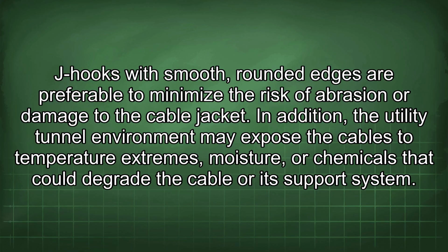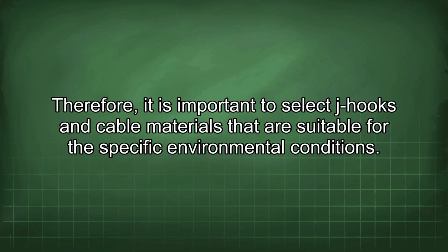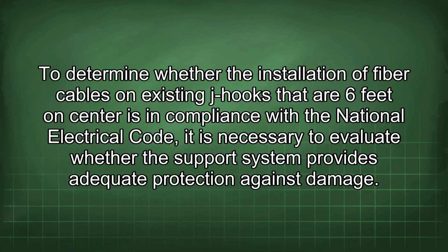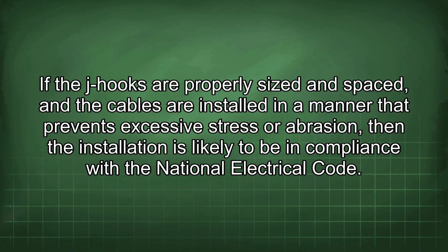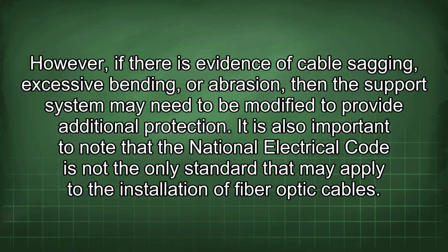In addition, the utility tunnel environment may expose the cables to temperature extremes, moisture, or chemicals that could degrade the cable or its support system. Therefore, it is important to select J-hooks and cable materials that are suitable for the specific environmental conditions. To determine whether the installation of fiber cables on existing J-hooks that are 6 feet on center is in compliance with the National Electrical Code, it is necessary to evaluate whether the support system provides adequate protection against damage. If the J-hooks are properly sized and spaced, and the cables are installed in a manner that prevents excessive stress or abrasion, then the installation is likely to be in compliance with the National Electrical Code. However, if there is evidence of cable sagging, excessive bending, or abrasion, then the support system may need to be modified to provide additional protection.